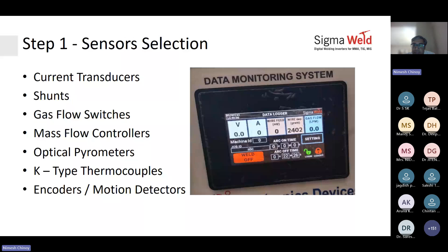Now this is what a CT looks like. A CT is a current transducer. You put the bus bar through the CT; this is a split-open CT, so you can put it across the welding cable or the power cable, or use a copper bus bar through it. It captures the current flowing through the cable via magnetic interference, and translates that into a signal ranging from minus 15 to plus 15. This signal is then interpreted by the microcontroller or PLC to find out the voltage and current level you are welding at. The CTs have a rating.